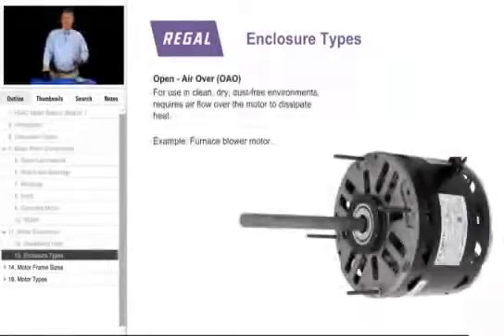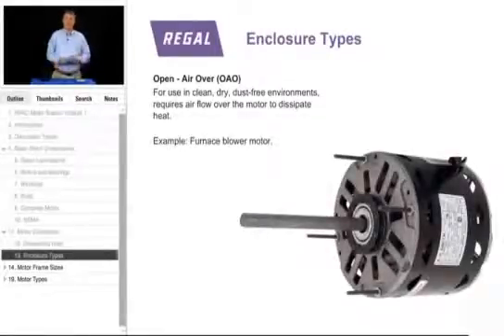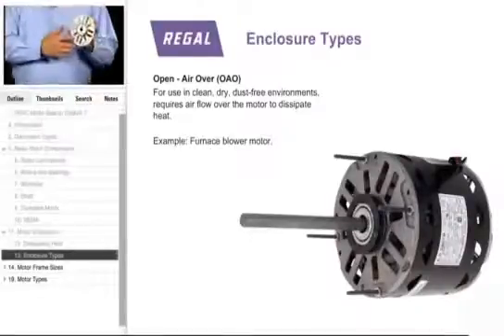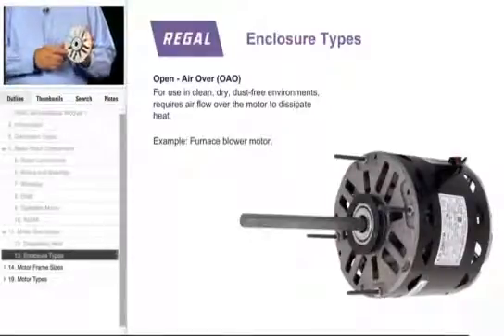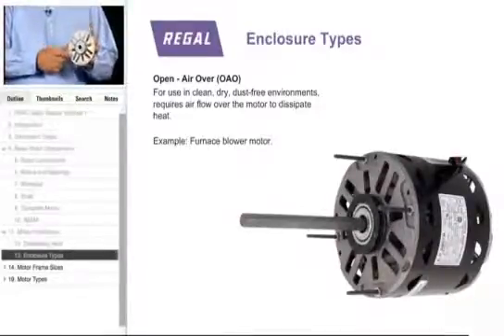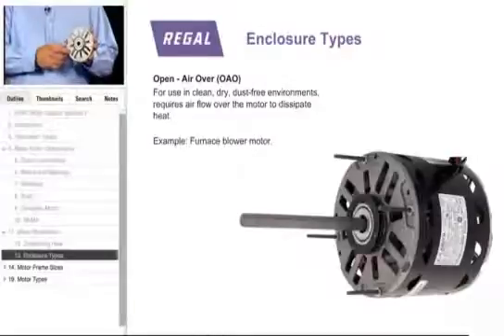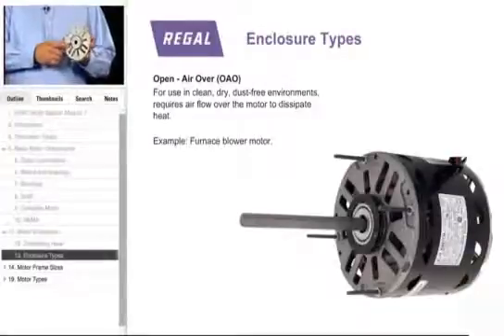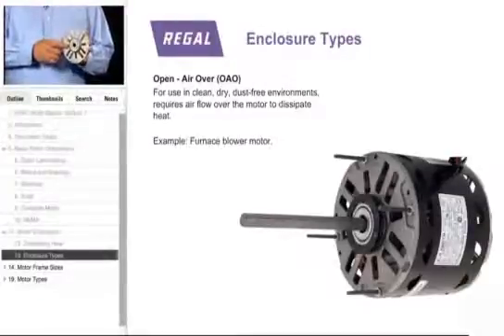The first type of enclosure is an open air over, or OAO, construction. There will typically be holes in the end frames or end shields and in the shell of the motor. This is used in a typically clean, dry, dust-free environment — a typical furnace blower motor.